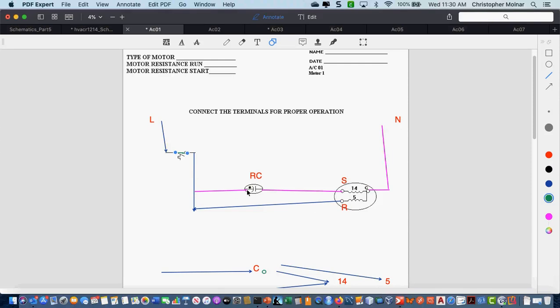At the same time, it provides power to my run capacitor, which slightly delays the current going to my start winding. Therefore, my magnetic field is going to be a little bit delayed in the change from north to south on that start winding. The motor turns, it runs efficiently because I never am losing my magnetic field. Common connects back to neutral. Pretty simple operation. Now, let's make a change to my schematic diagram that I started.